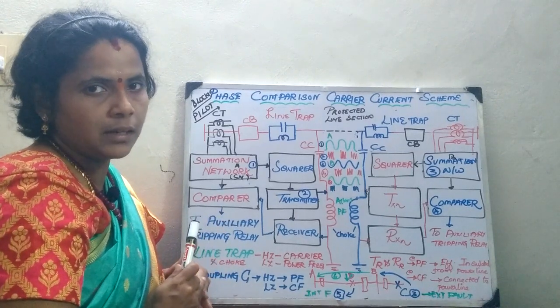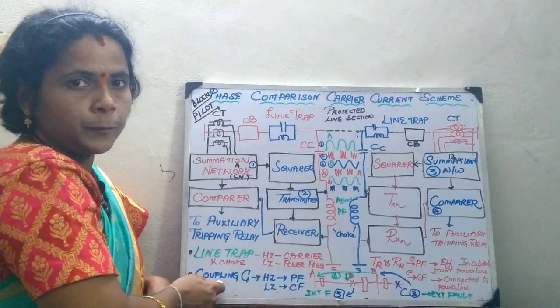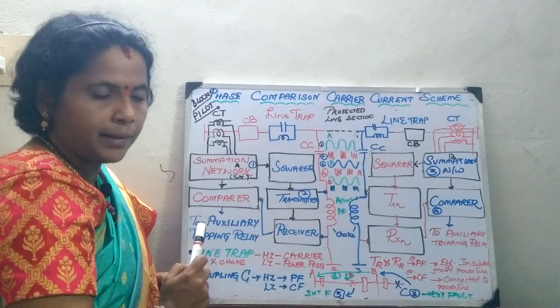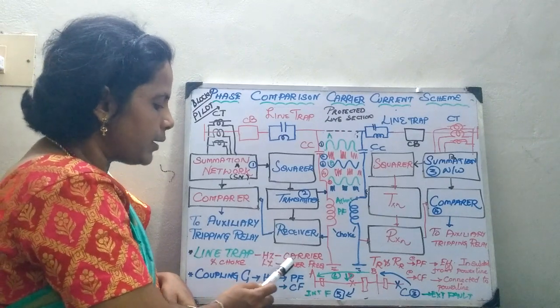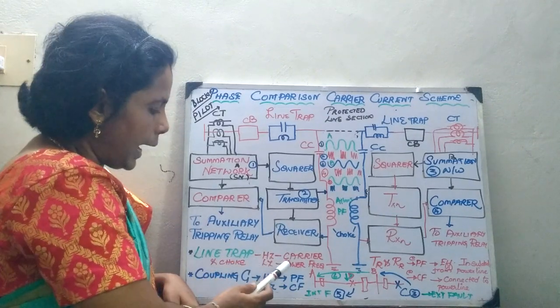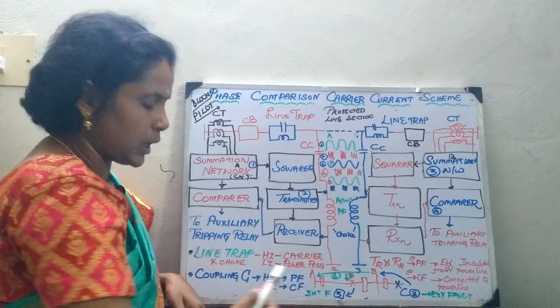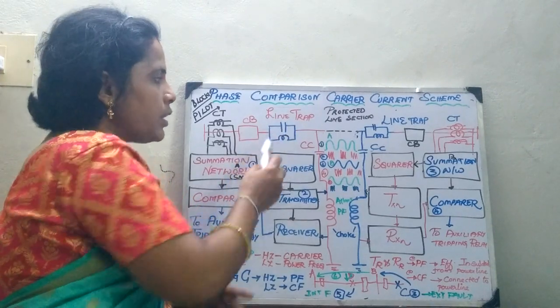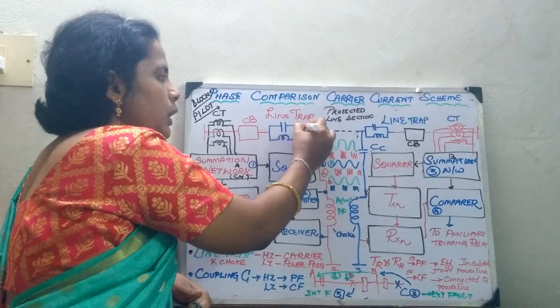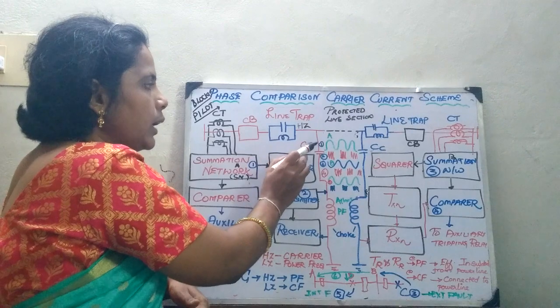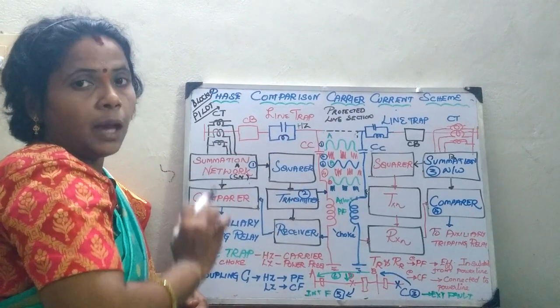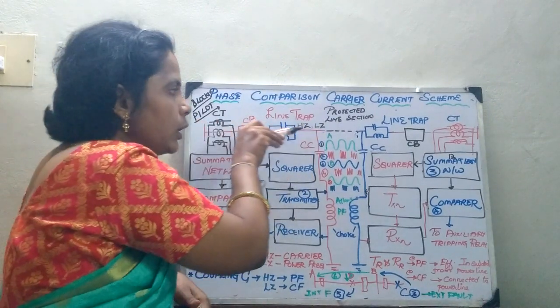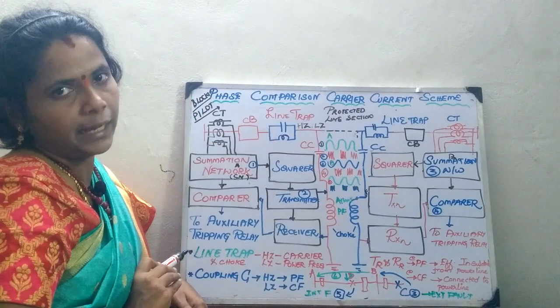Now we will see the three main components and their functions. The first is the line trap — a parallel resonance circuit that offers high impedance to the carrier frequency and low impedance to the power frequency. This means it does not allow the carrier frequency to mingle with the power line, but allows only the power frequency to pass through.